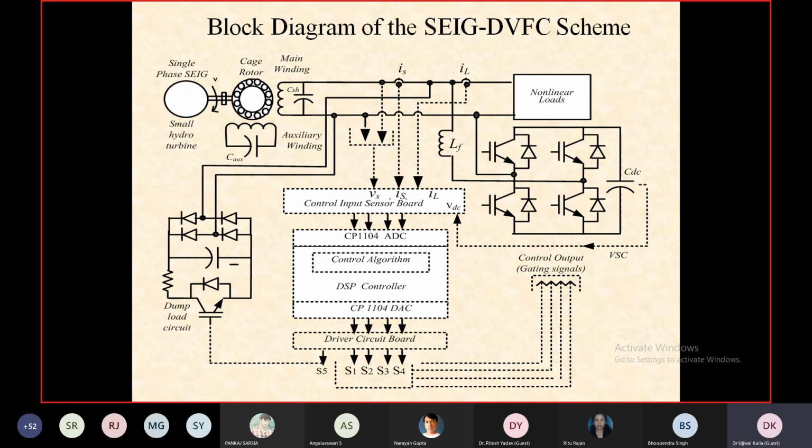But in direct control techniques, algorithm is required to detect the magnitude of individual harmonics. इनडायरेक्ट कंट्रोल में तो हमने ये नहीं पता लगाया था कि थर्ड हार्मोनिक्स का मैग्नीट्यूड कितना चाहिए लोड को, फिफ्थ हार्मोनिक्स का मैग्नीट्यूड कितना चाहिए, सेवंथ हार्मोनिक का मैग्नीट्यूड कितना चाहिए. That we have not calculated in the control. Just we have put the restriction on the generator that it will supply only the fundamental component of the load current. Nothing else we have done.